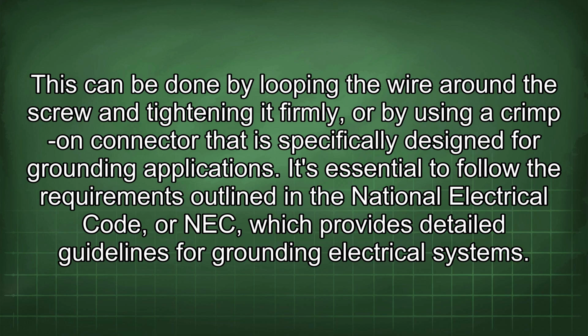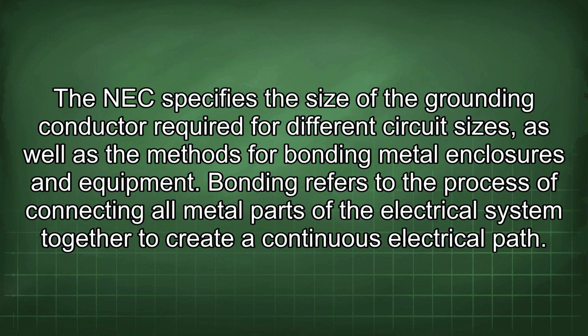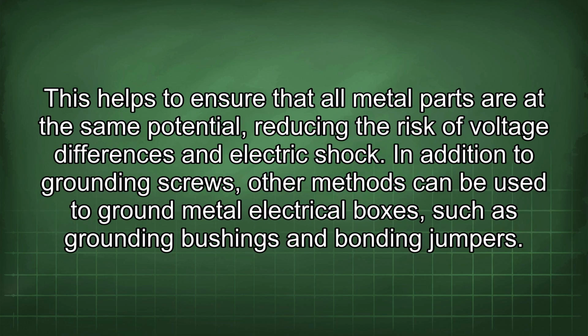It's essential to follow the requirements outlined in the National Electrical Code, or NEC, which provides detailed guidelines for grounding electrical systems. The NEC specifies the size of the grounding conductor required for different circuit sizes, as well as the methods for bonding metal enclosures and equipment. Bonding refers to the process of connecting all metal parts of the electrical system together to create a continuous electrical path.